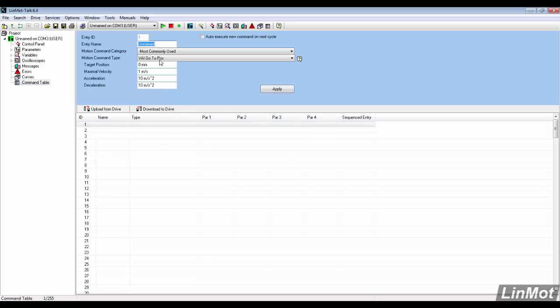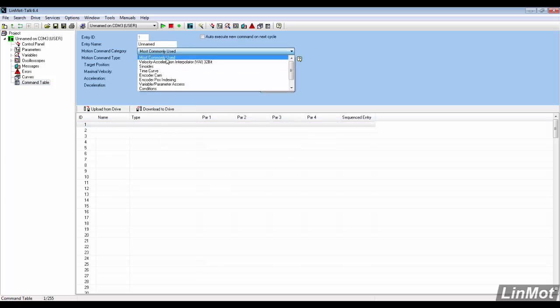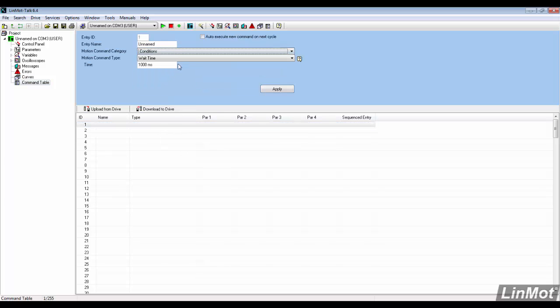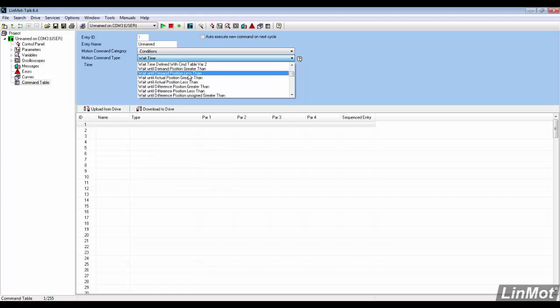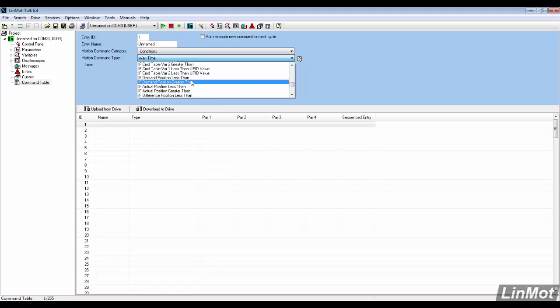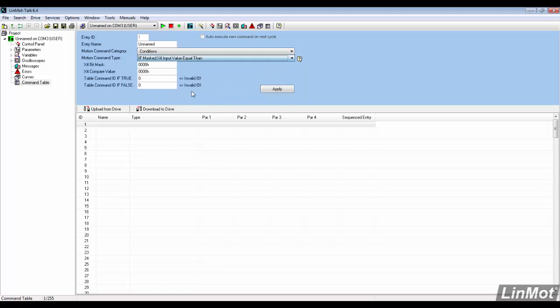Since motion will be continuous, a way to stop it is needed. Under conditions, we are looking for if masked X4 input value equal then. Since X4 is the input, the X4 bit mask and the X4 compare value are both set to 0002.